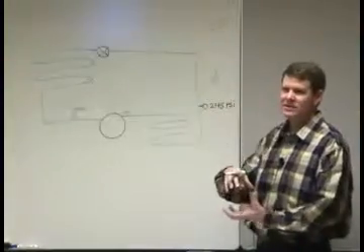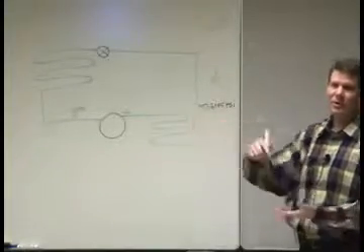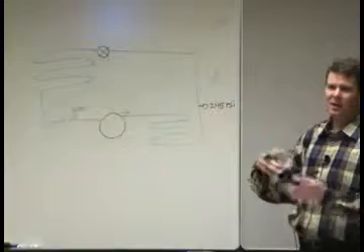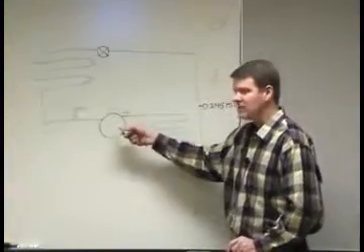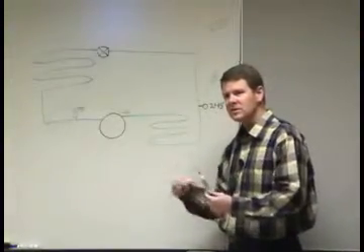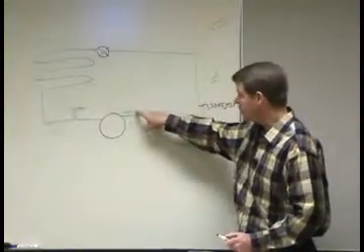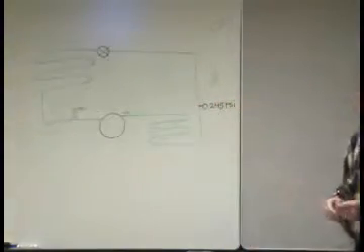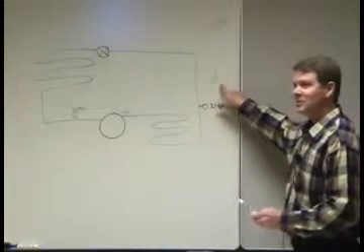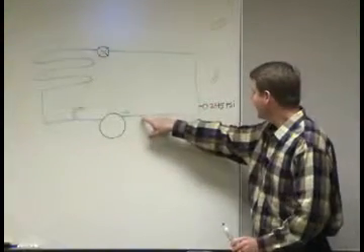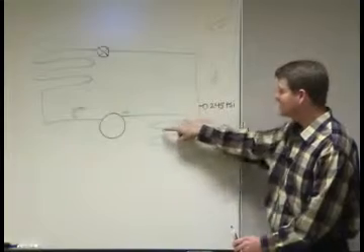When that compressor is compressing that vapor, anytime you take 10 pounds of vapor and put it in a 1 pound bag, you're cramming all those molecules, you're creating a lot of friction, and it generates a lot of heat. With the heat of the mechanical piston, scroll, whatever you got, the motor and the compressor, we're adding a lot of heat to that vapor. So it's going to come off of here a lot hotter than 115 degrees. It's probably going to be 20, 30 degrees hotter than that. Hot enough you won't want to put your hand on it. So it comes off of there smoking hot, 245 pounds, and goes into this coil.